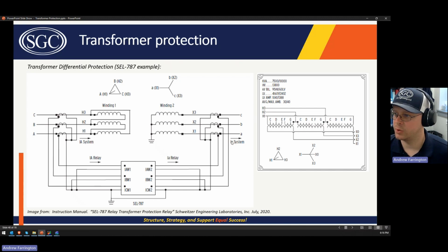This is our transformer that we're going to protect. One of the things that I really want to point out here is that the CT connections to our 787 relay are what you would expect. They're standard connections, right? So the A phase CT is wired into the A phase current input, B to B, C to C, and so on. Winding 1 is on the high side of the transformer, the delta side, and winding 2 is on the low side of the transformer, which is pretty typical, but your relay may not be set up that way, right? So you need to pay attention to this.